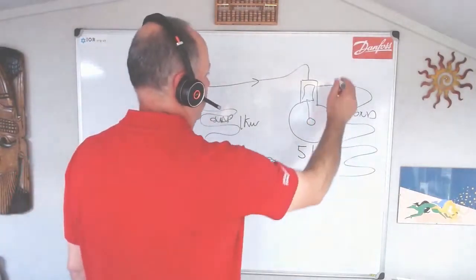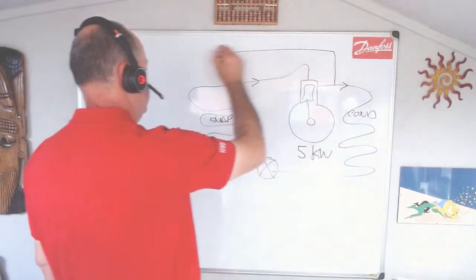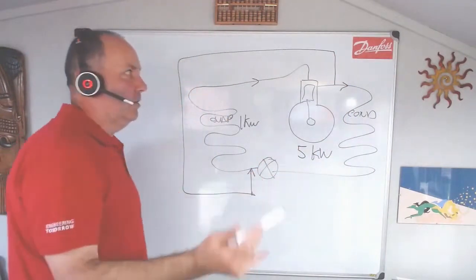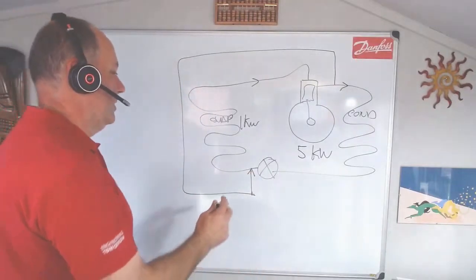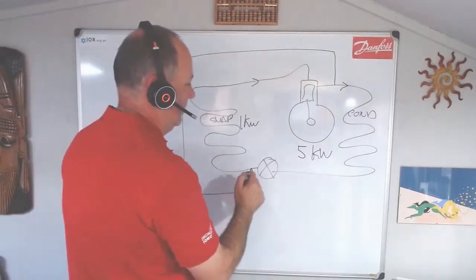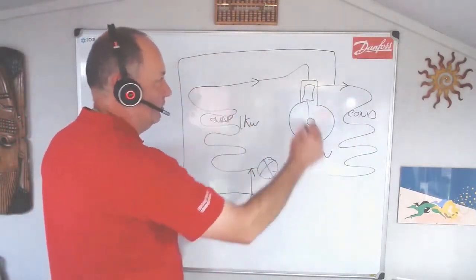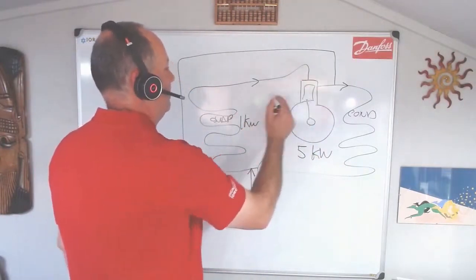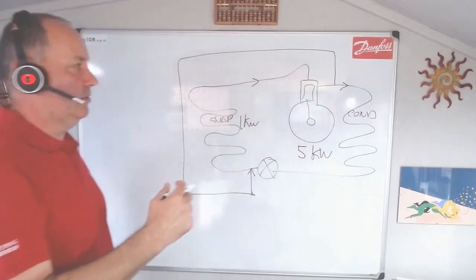We could do a hot gas bypass and take a bit of the discharge gas and dump it into the evaporator here, a bit like a hot gas defrost. But we've got to be careful because the system is still running, and we've got to be careful of the temperature coming back to our machine because we need to keep an eye on the superheat.